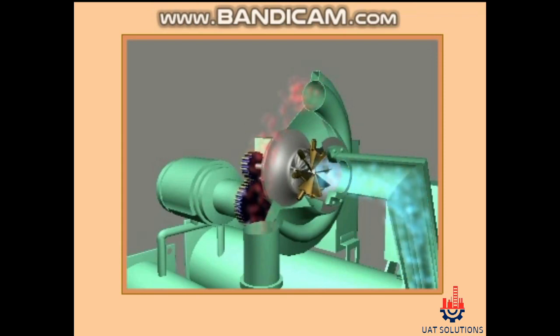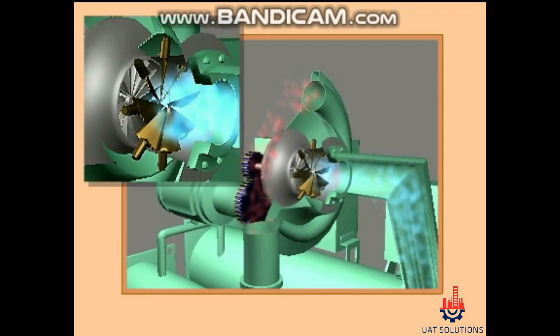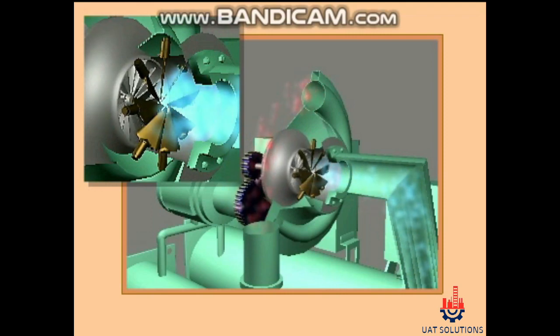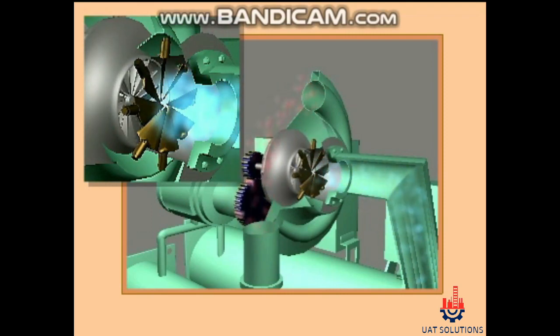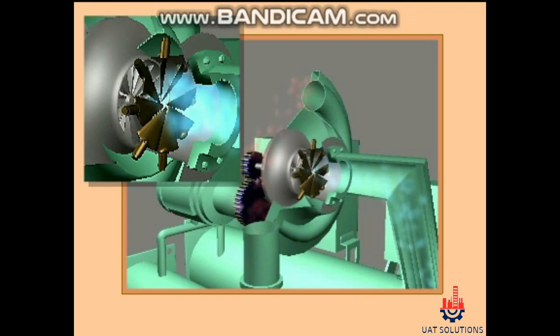As the load on the chiller decreases, the pre-rotation vanes begin to close and restrict the amount of refrigerant vapor entering the eye of the impeller, which reduces the amount of refrigerant being circulated.